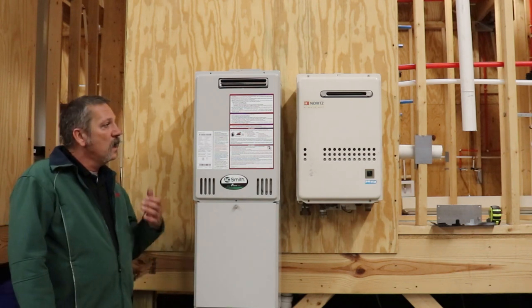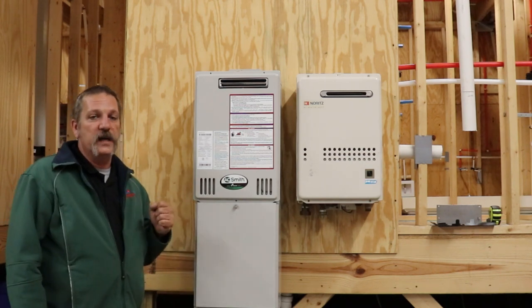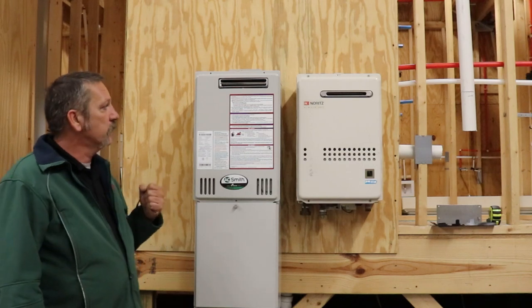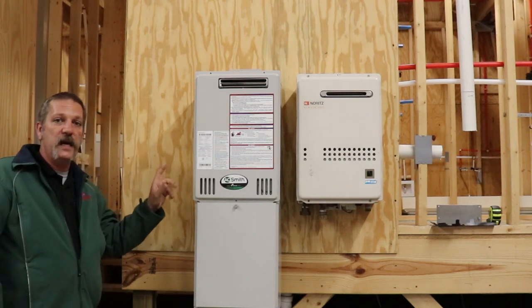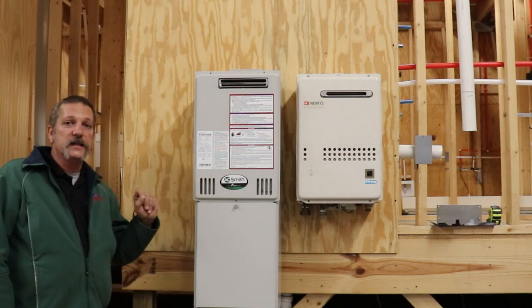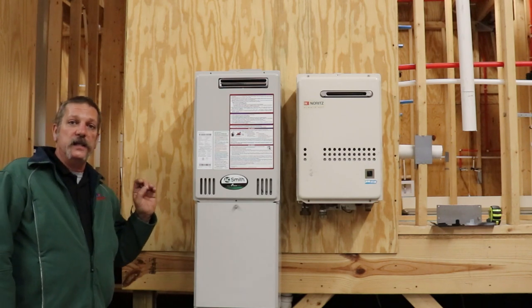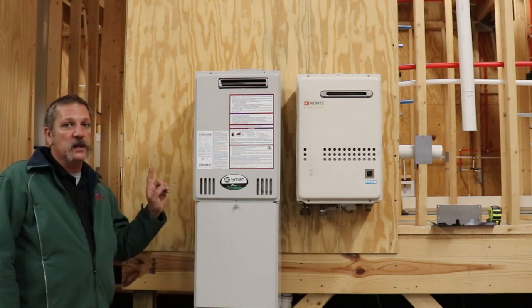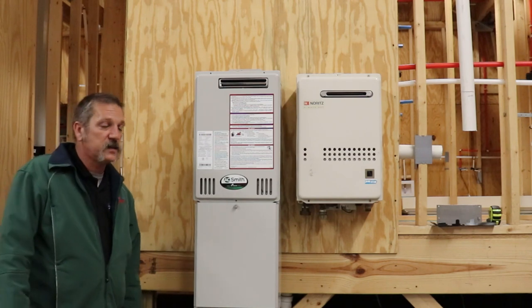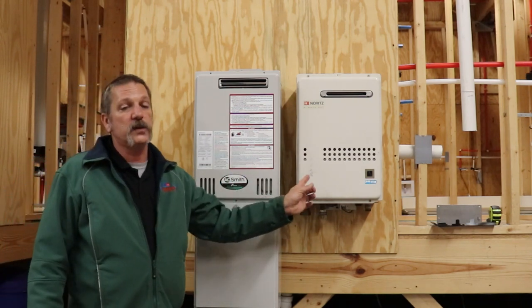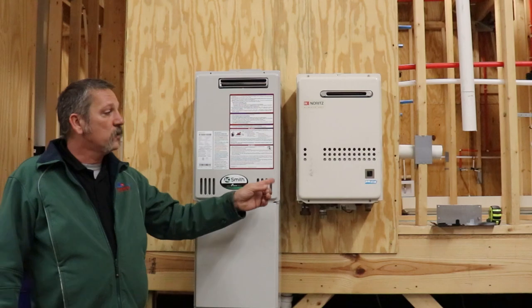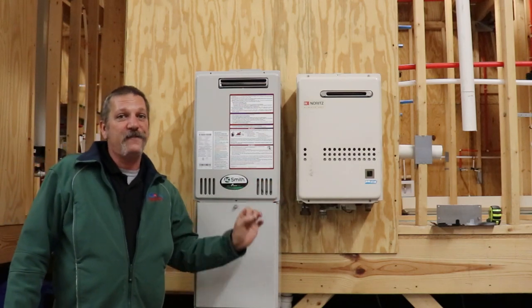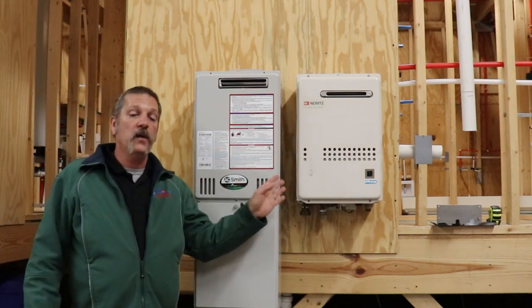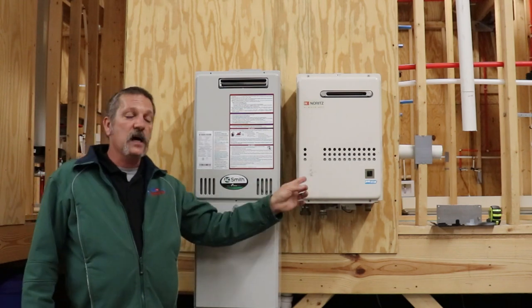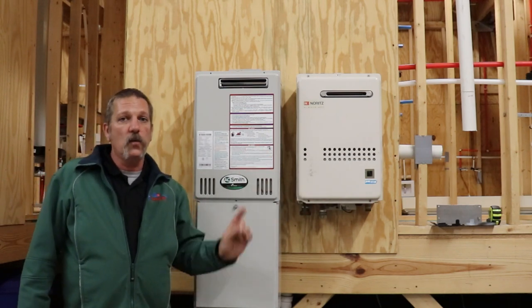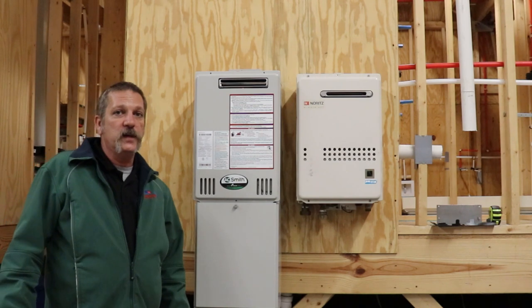Now, our UEFs on this, our Uniform Energy Factor. Your non-condensing, this particular one here, is going to land right about 0.82, which is a lot higher than that conventional tank style. This one over here, which is the condensing, is going to land right about 0.95, which is a lot better than all of them. The condensing ones are the most efficient water heaters pretty much out there that you can get right now.